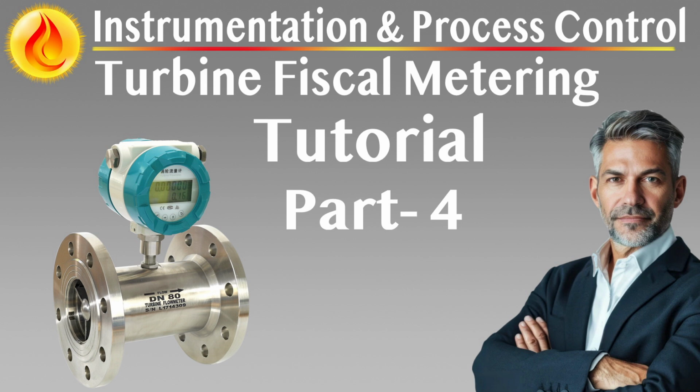Station microcomputer centralized aggregation, reporting, and operator interface. The station microcomputer serves as the central control node for the Fiscal metering system. It must collect, process, and display data from all stream microcomputers and manage system-level functions such as sampling, net oil computation, alarm processing, and reporting.